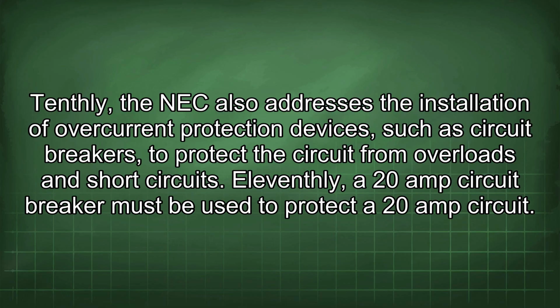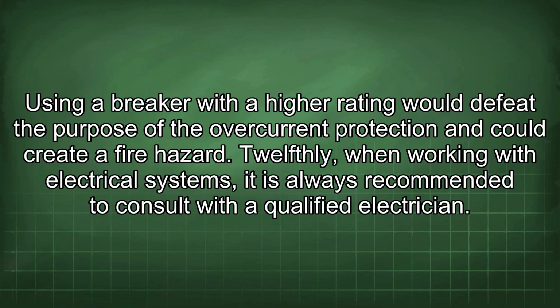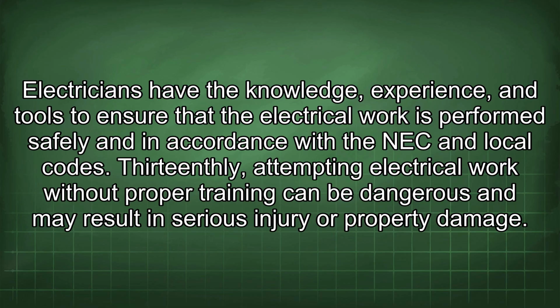Tenthly, the NEC also addresses the installation of overcurrent protection devices, such as circuit breakers, to protect the circuit from overloads and short circuits. Eleventhly, a 20 amp circuit breaker must be used to protect a 20 amp circuit. Using a breaker with a higher rating would defeat the purpose of the overcurrent protection and could create a fire hazard. Twelfthly, when working with electrical systems, it is always recommended to consult with a qualified electrician. Electricians have the knowledge, experience, and tools to ensure that the electrical work is performed safely and in accordance with the NEC and local codes. Thirteenthly, attempting electrical work without proper training can be dangerous and may result in serious injury or property damage.